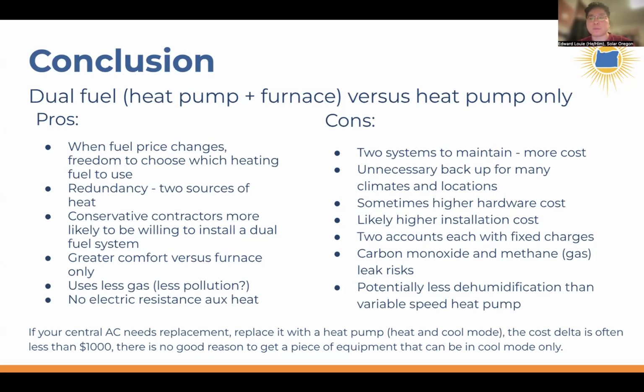And then also with a dual fuel system where you have a cheap heat pump, which is typically single stage, you potentially have less dehumidification than with a variable speed heat pump. But here in Oregon, it's not that big of a deal. We don't really have a humidity issue. This could become a big topic to discuss if we were in the American Southeast where it's very humid, but we're not. And if your AC goes out, there's really no reason not to get a heat pump to replace that central AC. The cost delta is really small, and you gain a lot of comforts. So that's a really important point to take away from this presentation.